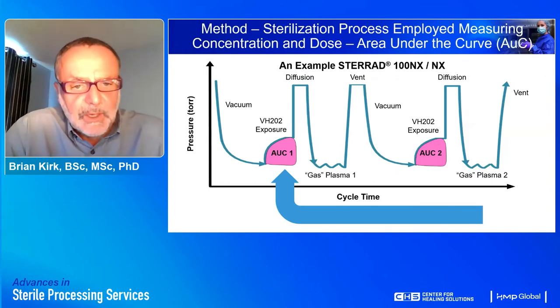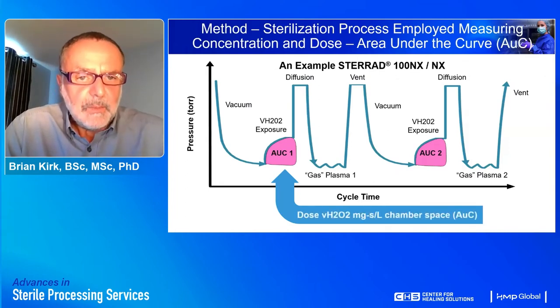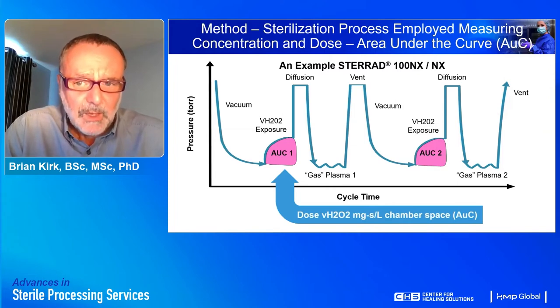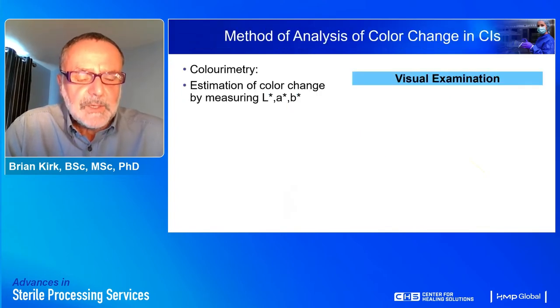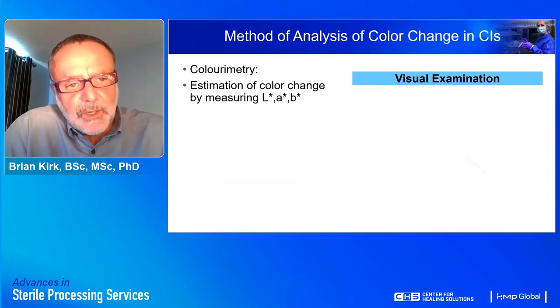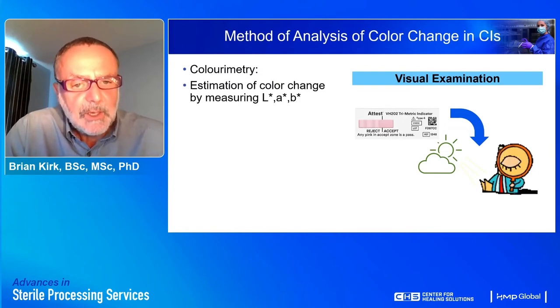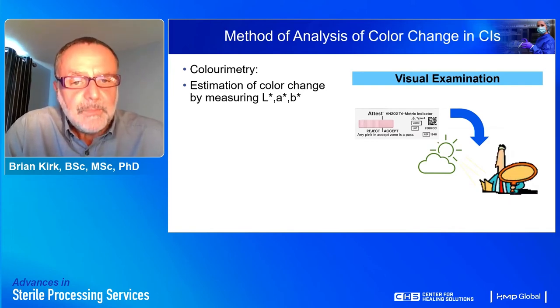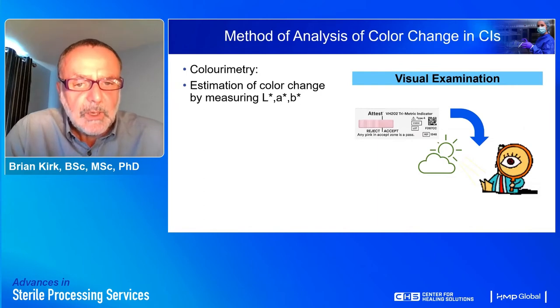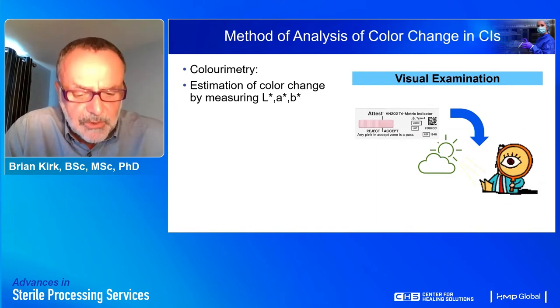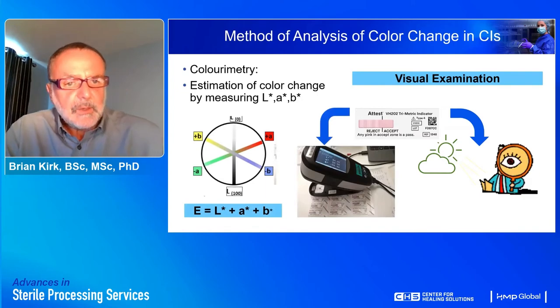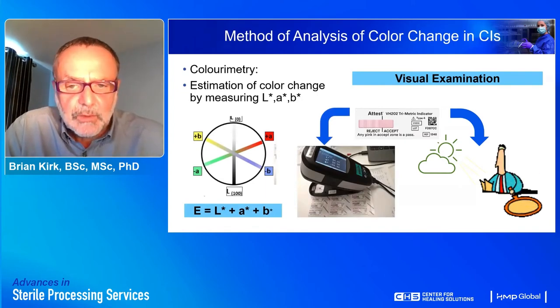The sterilization cycle was either an express or standard cycle. The color change on the CIs was analyzed by two methods: first, by visual examination according to the manufacturer's instructions — each chemical indicator was examined in good light conditions by a single observer, and color change results were interpreted according to the manufacturer's instructions.